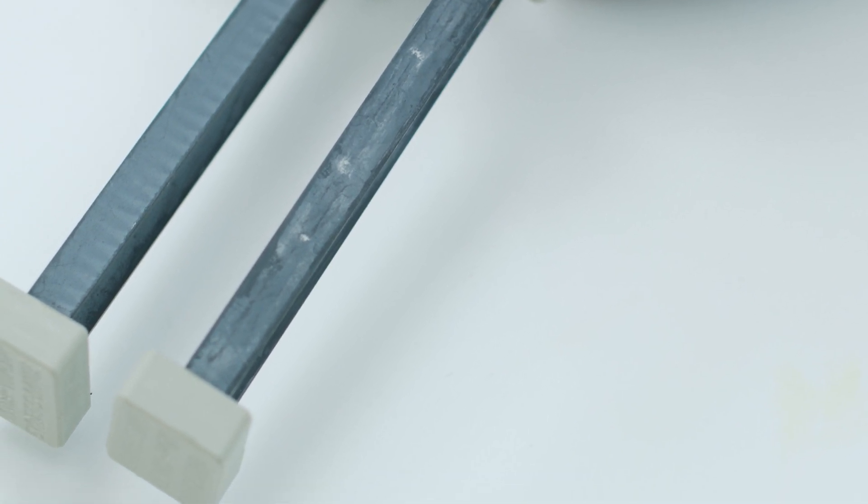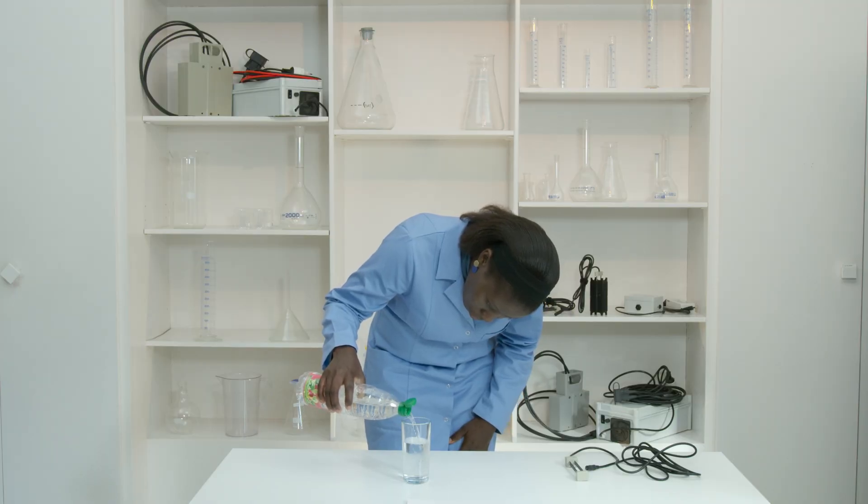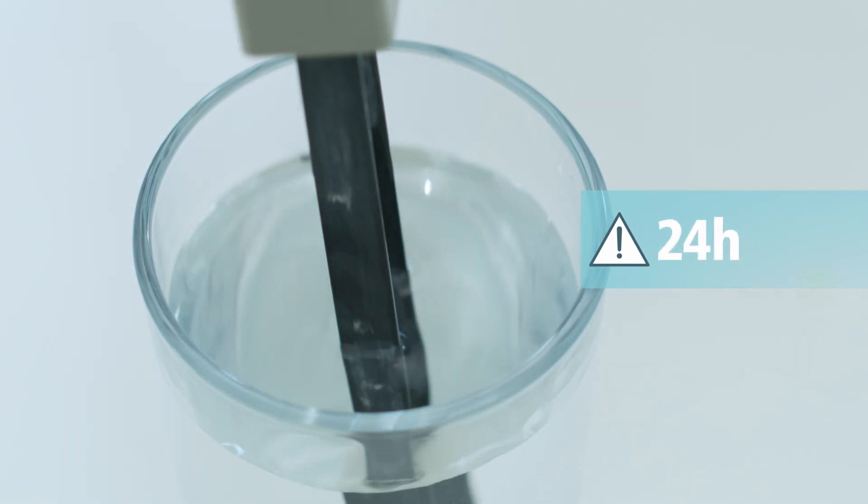If deposits appear on the electrode, soak the device in a vinegar solution, 50% water and 50% vinegar, for 24 hours.